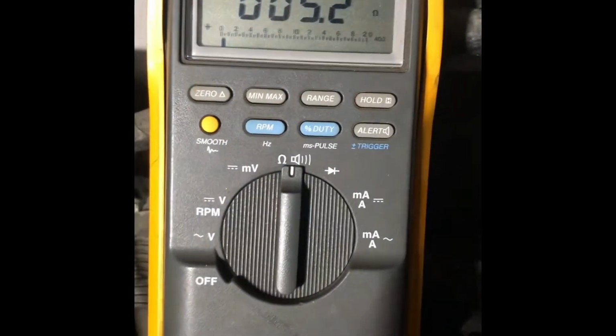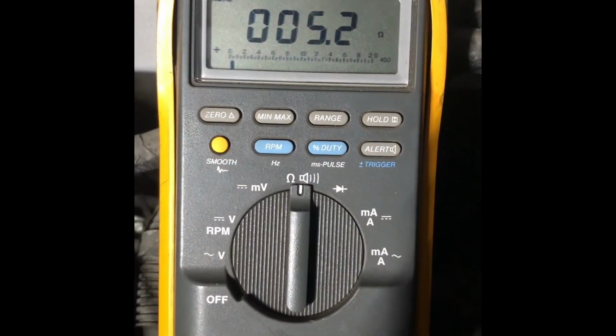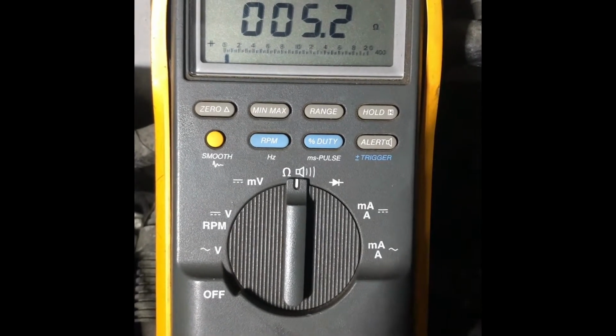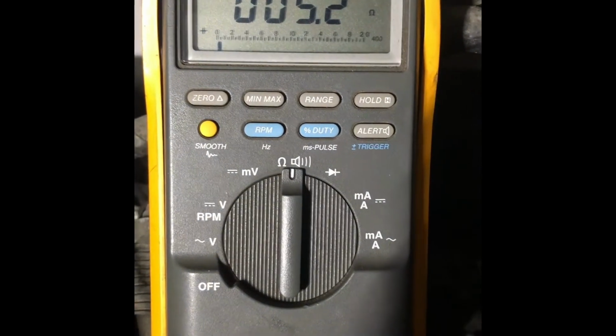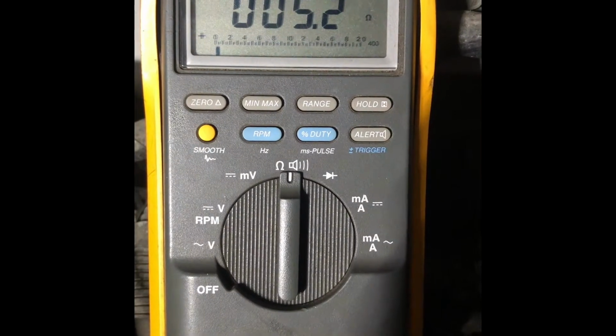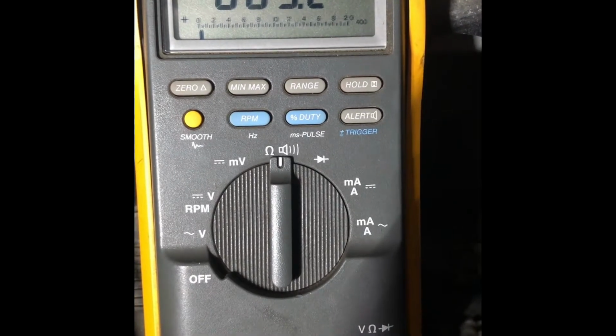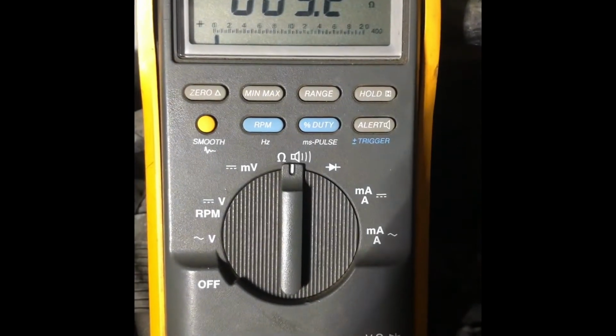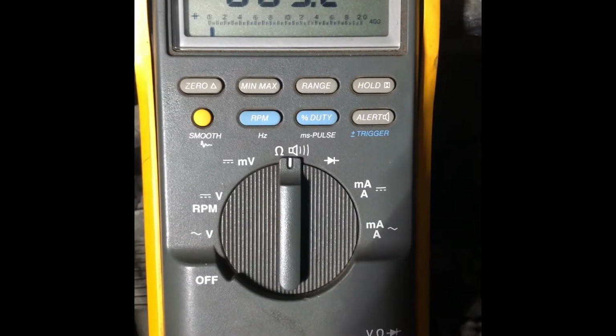So this is a good test, because if this solenoid was bad internally, sometimes it'll be so different. Like instead of 5.2, I might have 25 or 120, whatever, and that's a good indication. But in general, I don't believe that resistance is a good check.